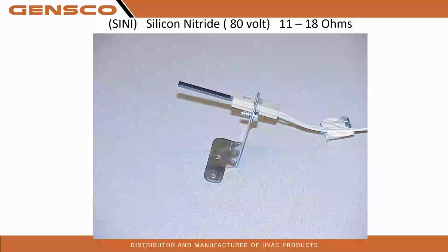An easy way to identify them, for the most part, is the square ceramic body. Most 120 volts, I say most 120 volts, are round in the ceramic department, and the 80s were typically square. It's a good rule of thumb, but that does not always correlate. So this is an 80-volt igniter. It's 11 to 18 ohms. Some manufacturers let them go much higher than that, but we are going to stick with this one, 80-volt, 11 to 18 ohms at room temperature.